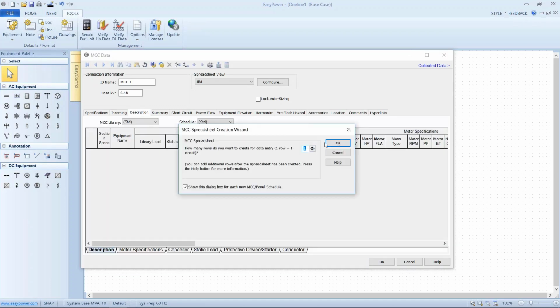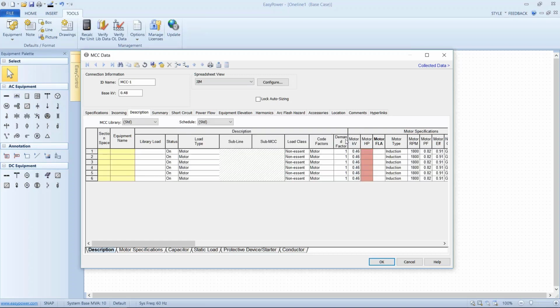When I start to do descriptions of my loads, I have multiple choices. Frequently, if I do use motor control centers a lot, and if I do have some common configurations, the tool allows me to set up a library, an alternate library that I can select library loads from. So in this case, and I did this in the device library, I've set up an MCC test, referred to it as 480 volt generic.